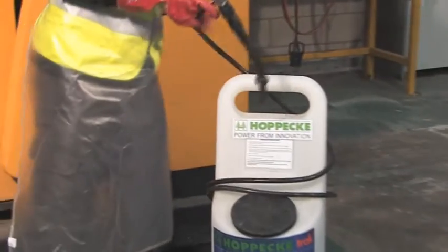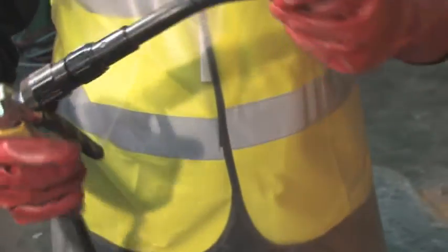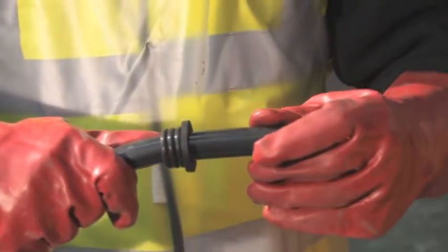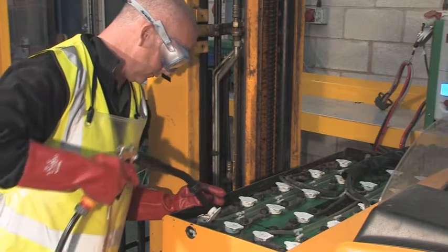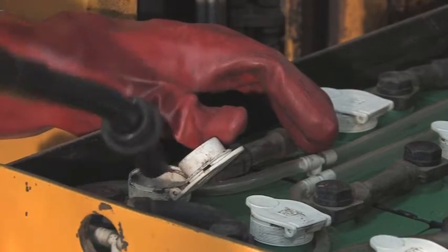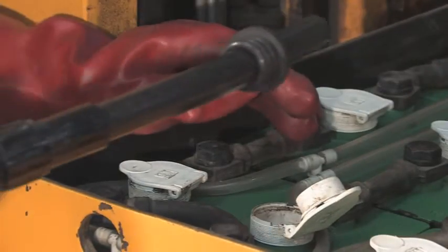It is always best practice to top up your batteries immediately after charging when the batteries are fully charged. Using distilled water, fix the gun securely to the tubing, then adjust the automatic battery water level topping gun to the required level. Fill each cell separately, removing any residue of water and closing each cell cap before moving on to the next.